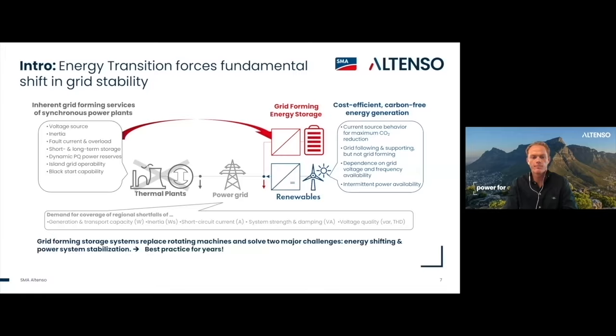And that's being done internationally. It's something that I know that Eskom is looking into, because they're engaged with SMA and Altenso to understand what is best practice from a grid perspective when you implement grid forming projects according to different jurisdictions in the world and different grid operators. And so that's not only important from a grid level and from a total system perspective, but this technology can also be used by industrial customers to essentially enable an energy security from the grid using grid forming technology and black start functionality.